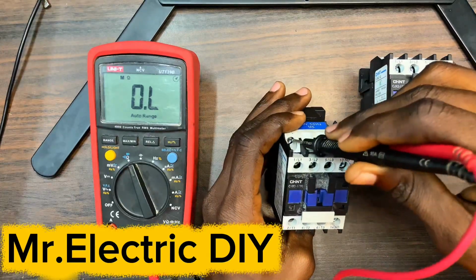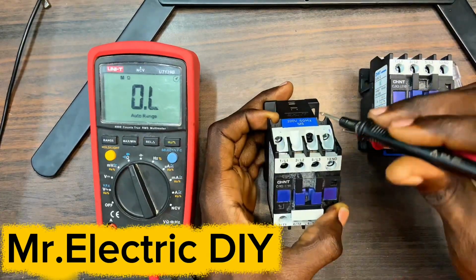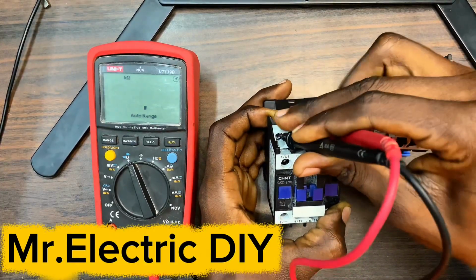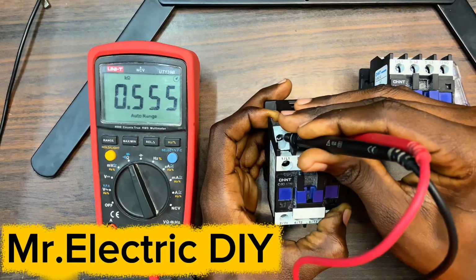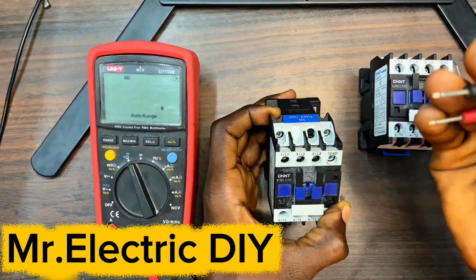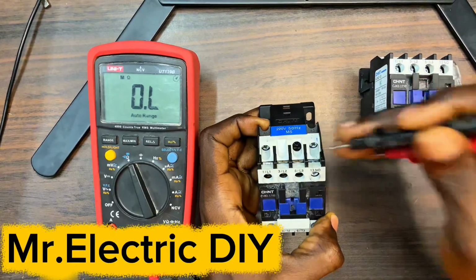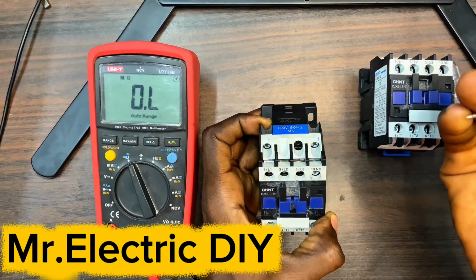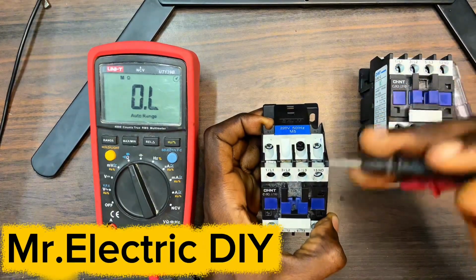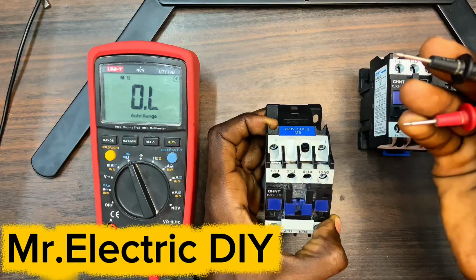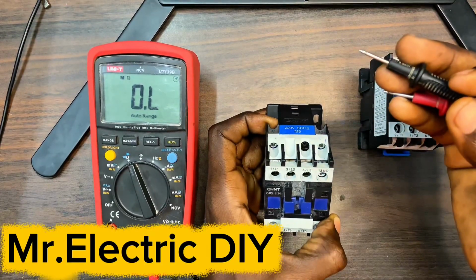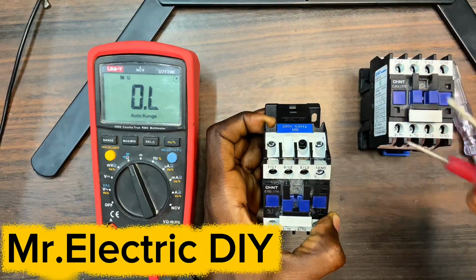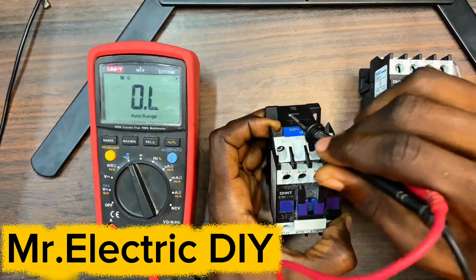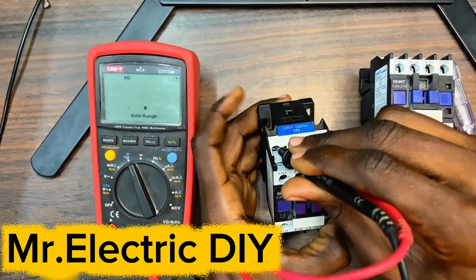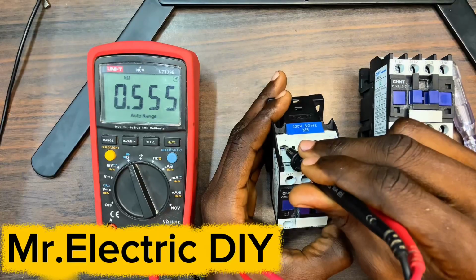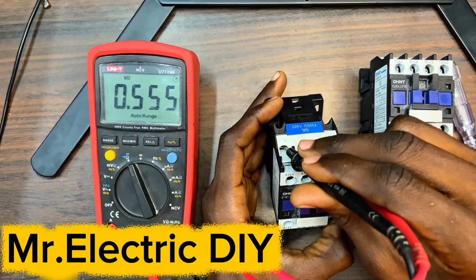With the checking of the coil ohmic value, if the ohmic value of the coil is near zero, it means that there's a short circuit. And also, if you're having an infinite value, it also means that the coil inside this contactor has broken. If you're having an infinite value or near zero ohms, meaning something is wrong with the contactor coil. Now we are having OL, I haven't connected it to anything. So even if you connect it to the coil terminals and the OL is showing open loop, meaning something is wrong with the contactor coil.